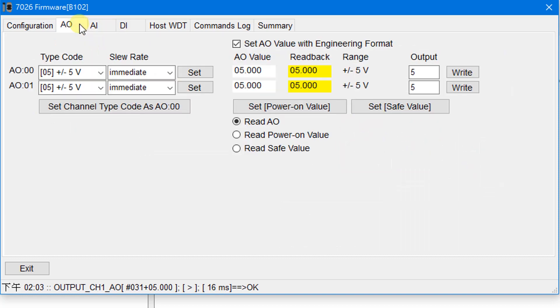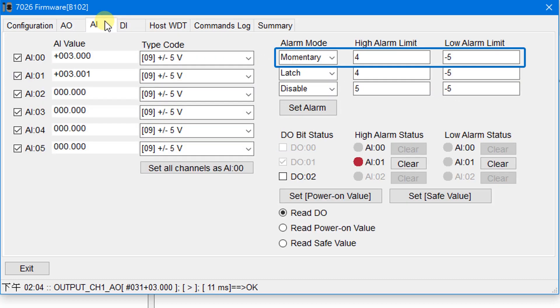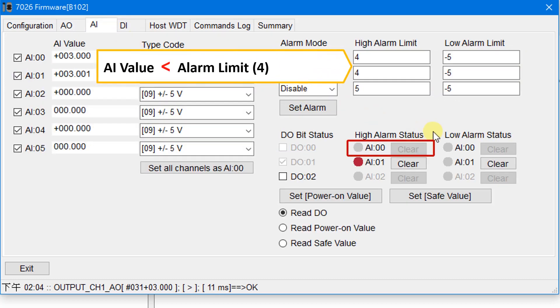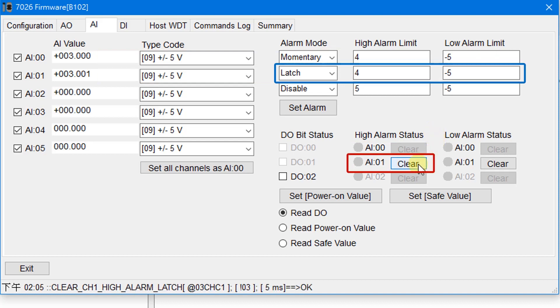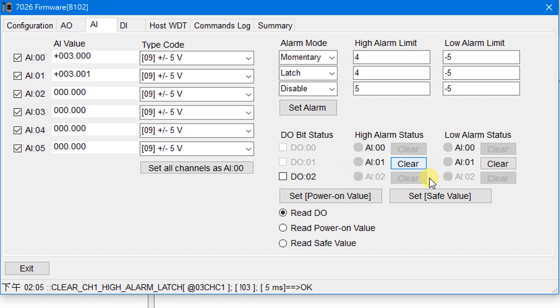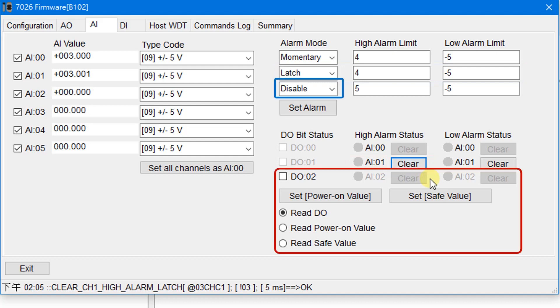Go to the AO page and set both output values to 3. Go back to the AI page — in momentary mode, the alarm notification will be automatically cancelled when the AI value returns to normal. When the alarm mode is set to latch, the user needs to manually remove the alarm notification. When the alarm mode is disabled, the DO can be used for general purposes.